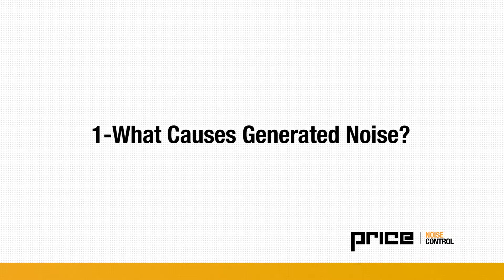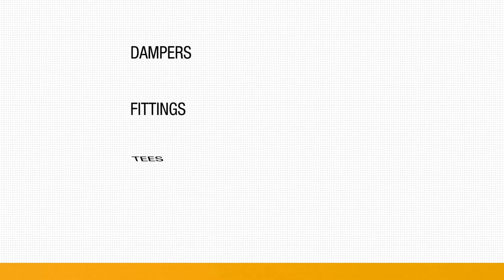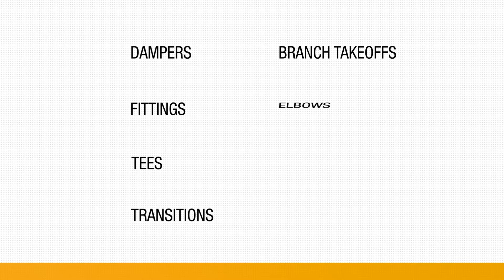What causes generated noise? In duct systems, airflow turbulence can occur at numerous elements including dampers, fittings, tees, transitions, branch takeoffs, elbows, air devices, and silencers. While mechanical equipment is often the source focused on during acoustical discussions, noise generated by duct elements can drive the occupant noise levels, especially when elements are in close proximity to the receiver. It's important to consider generated noise especially at higher duct air velocities and when low noise levels are required.